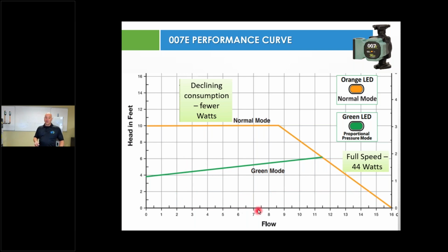So what you will learn over the next couple of weeks is I need to know the head loss of a heating circuit or of that indirect, and then I need to understand the flow rate in order to drive the BTU. So I'm going to ask a question here. If I have 10 feet of head, and I need to move 60,000 BTU, what would my flow rate be across here? And will that circulator handle that demand? Send those answers into Jim.